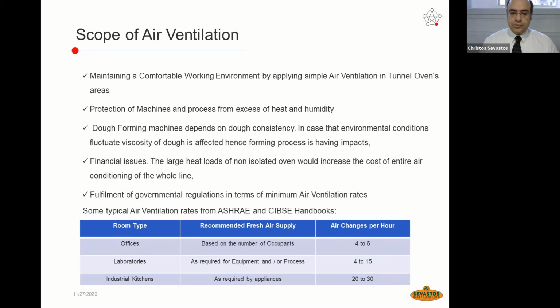In this table, we are referring to some kind of air ventilation rates which are governed by ASHRAE, in which you can see here a room type, which are rather irrelevant to a tunnel oven, but those air ventilation rates and air changes per hour are governing those three, let's say, segments. Offices, based on the number of occupants, 4 to 6. Laboratories, as required for equipment and process, 4 to 15. Industrial kitchens, as required by appliances, we mean here the heat sources, 20 to 30. We can see that this kind of air changes per hour is increasing in some kind of individual areas.